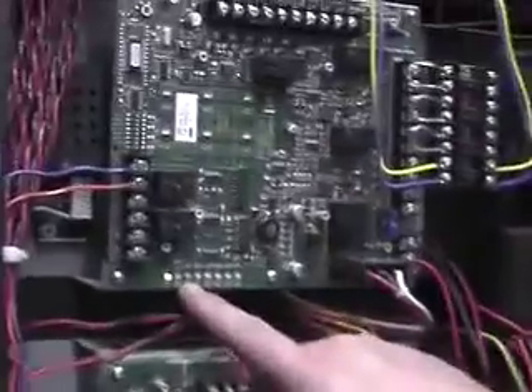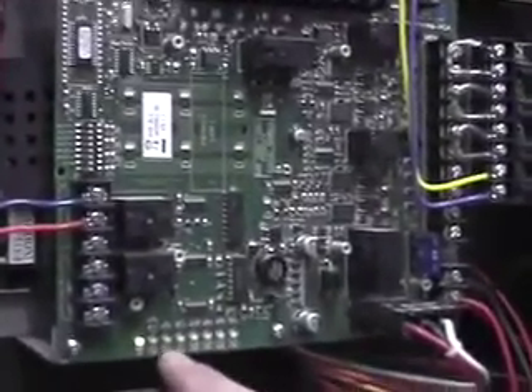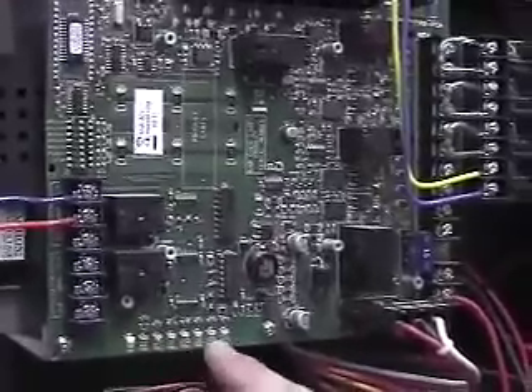On these power supplies, basically you have your lights here. Battery trouble, ground fault, signals 1 through 4. These newer power supplies have a reminder on the circuits. I wish they would have it on ground fault and the other faults, but they only have it on the circuits. It kind of helps you if you have an intermittent fault.